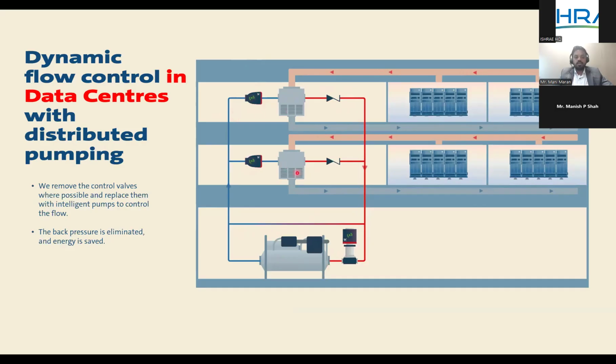So now each unit, or each load, has its own driver, and each unit's demand is addressed by its own driver. That's the difference we are trying to bring in the design, and this will eliminate the kind of friction created by the valves, and that is the saving we are seeing on the pump side. And more than that, we will see in detail how we have to design the system, and how we need to put it in the automation, so that the savings on both pumps and system level can be seen.